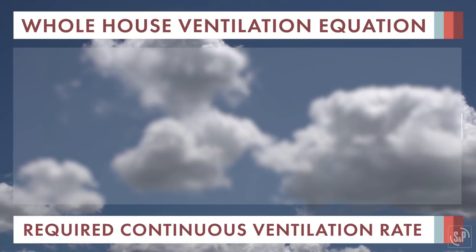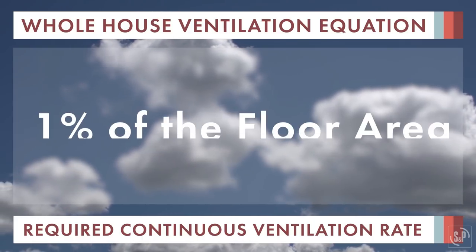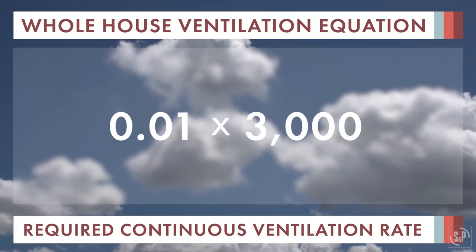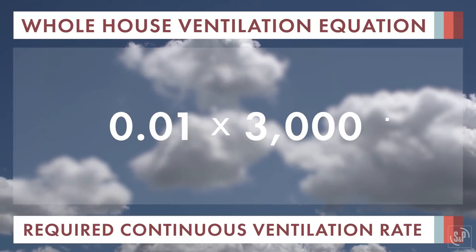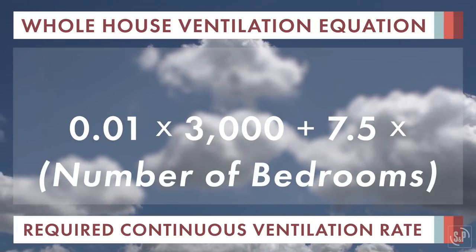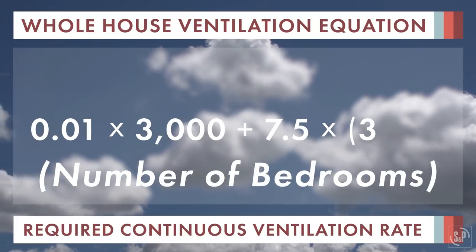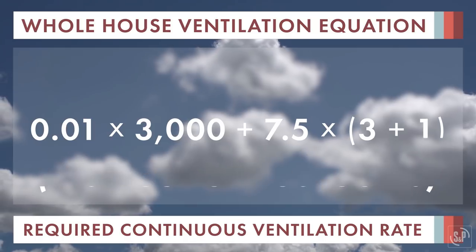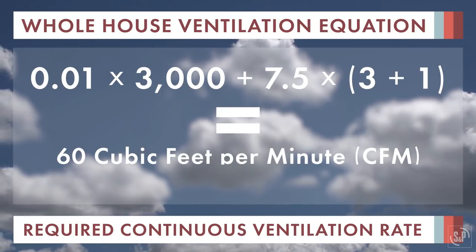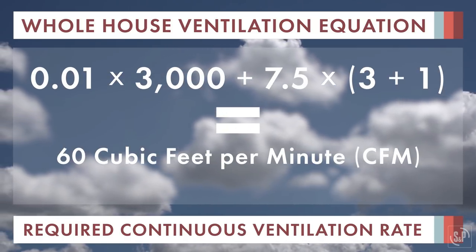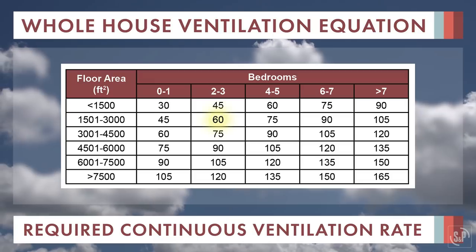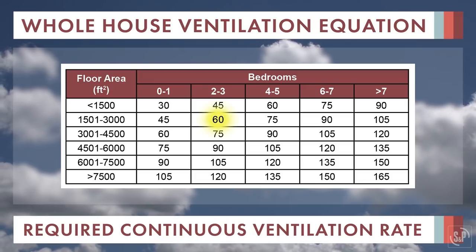Using the equation, you would take one percent of the floor area, which is three thousand, and add it to seven and a half times the number of bedrooms, which is three plus one, which equals 60 cubic feet per minute. You'll notice that you get the same CFM when using the table.